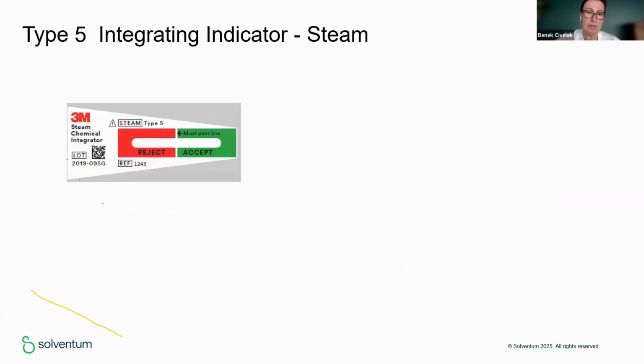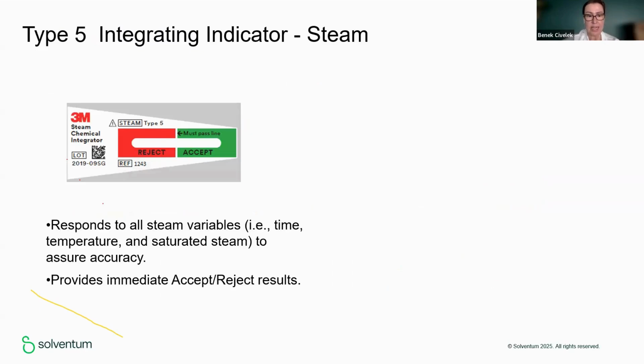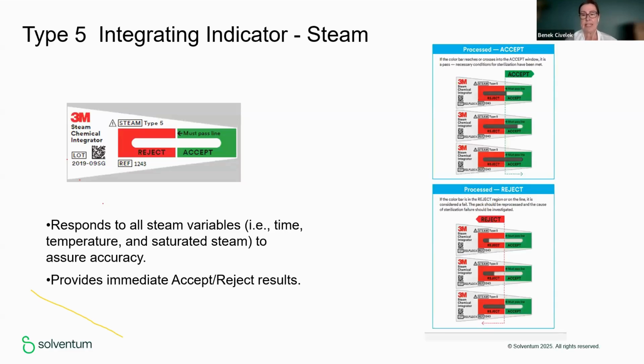This is an example of a type 5 integrated indicator from our solutions. And again, it can be used in every cycle, not for a specific cycle. And it will be easier to tell about pass or fail results because, as you can see in the chart, there is a threshold between reject and accept. So anything beyond the accept window will be accepted because every pack is different and their way of penetration of steam will be different. So it is not necessary that you see all the window black. Any movement beyond the accept window will be accepted.